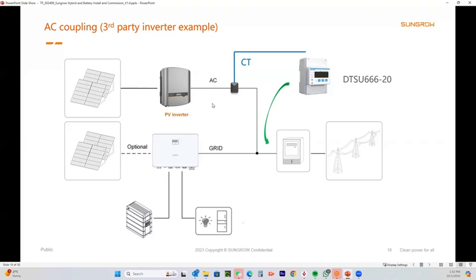This is AC coupling. Now the way it works is pretty much just the same. If this system here is producing more power than the loads are consuming, instead of exporting out to grid, the inverter will charge the battery from the AC to the DC of the battery, like this. So that's AC coupling. Now you might come across this, for example, if somebody already has a PV system installed and they want batteries, you can AC couple quite easily. You could replace the existing inverter if you want to. That's fine, you can do that. Bear in mind, however, if you do replace that inverter, you will become responsible for the warranty of the whole system. Whereas if you AC couple, you're not responsible for the warranty for this stuff here.